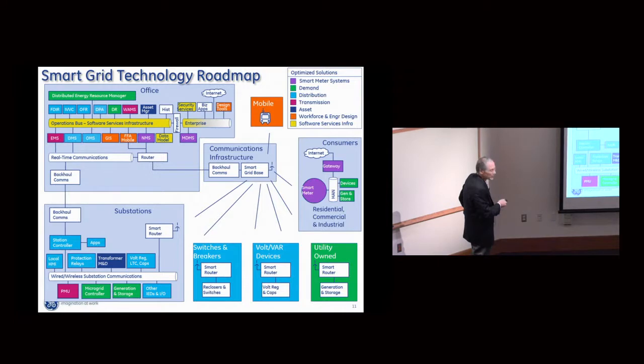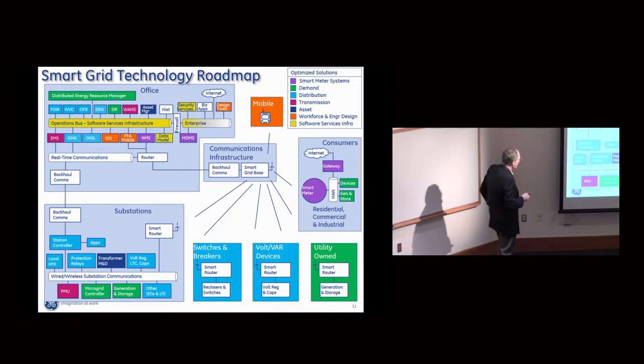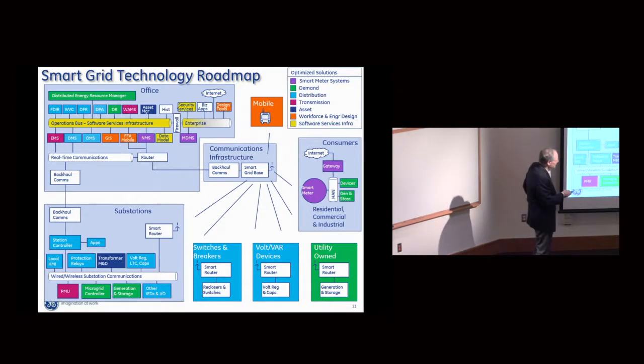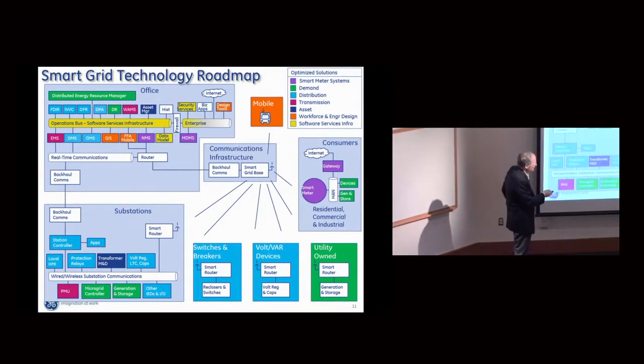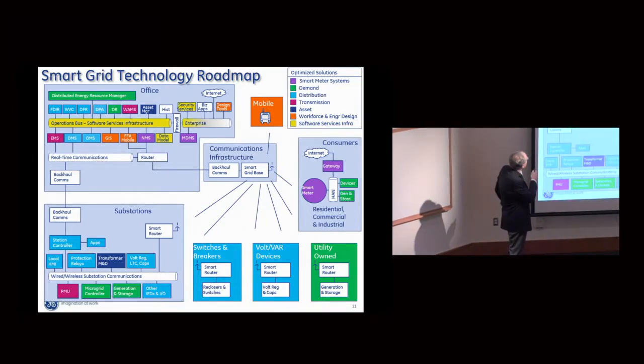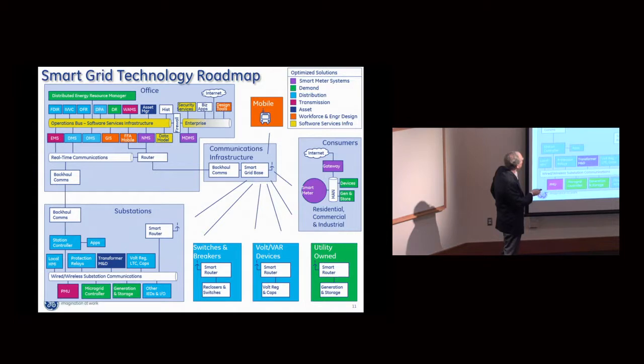At substations, we can run applications and distribute intelligence down at the substation level. Then, out on the feeders, I need sectionalizing devices to support the logic for fault detection, isolation, and restoration. I also need voltage regulators and capacitor banks to support the integrated Volt/VAR control logic, which could be located here or here.